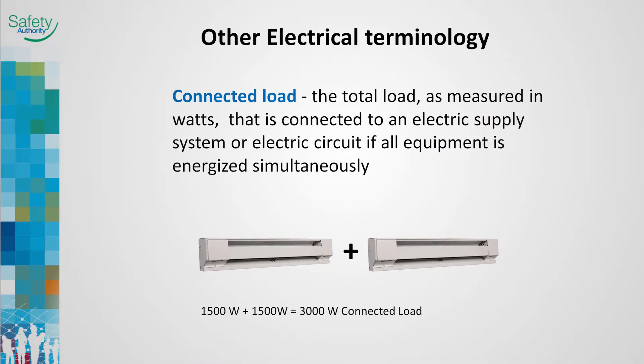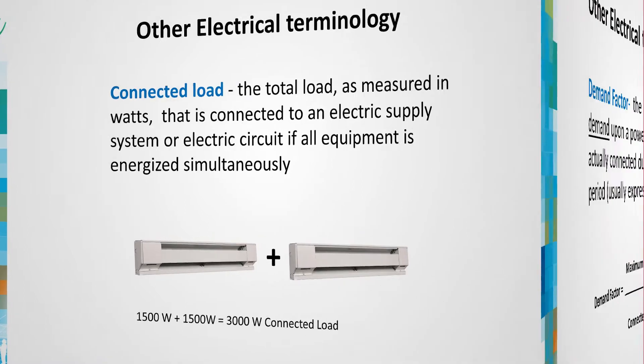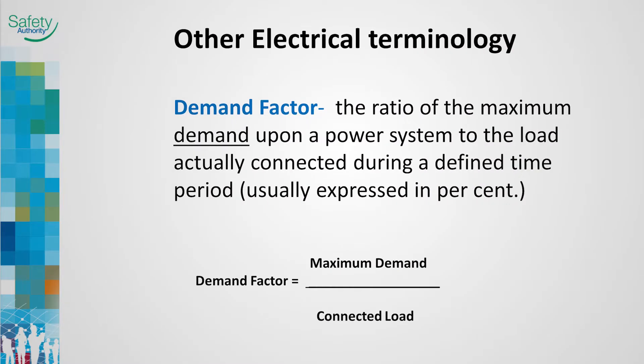Connected load is the total load measured in watts if all equipment is energized simultaneously. The connected load is a term used throughout the code but is not specifically defined in this section. Demand factors are based on the concept of diversity throughout an electrical system or circuit and are time dependent. This means the maximum load supplied by a power system may change during the day based upon electrical loads and processes required. Prescriptive demand factors are provided throughout the code in numerous sections.